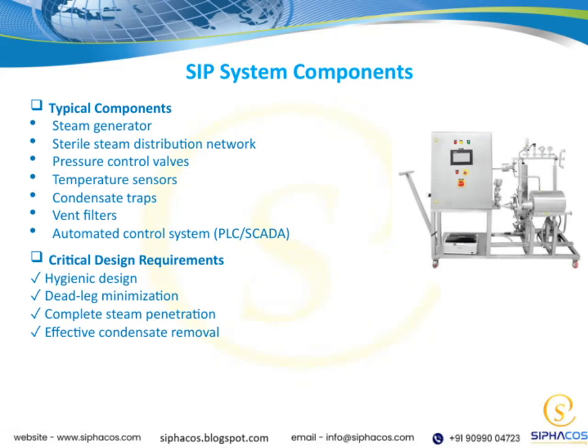Let's take a closer look at the key components that make up a typical SIP system. You've got the steam generator, which creates the steam. Then there's the sterile steam distribution network, pressure control valves, temperature sensors, condensate traps, vent filters, and the automated control system, usually a PLC or SCADA setup. But it's not just about parts. The design has to be hygienic, minimize dead legs where steam can stagnate, ensure complete steam penetration, and remove condensate effectively. These requirements are critical to keeping the system reliable and safe.